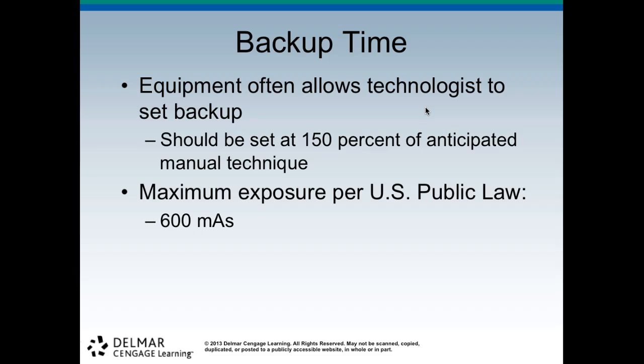The backup time: the equipment often allows the tech to set a backup time, and actually all the equipment does. It should be set at 150% of the anticipated manual technique. So if a hand is whatever technique, you're going to set 150% of what you normally shoot a hand or KUB at. You look at a person, let's just say they're 20 mAs, and you're going to take 150% of that and set it as a backup so it'll shut off.